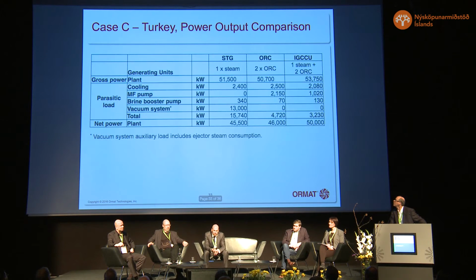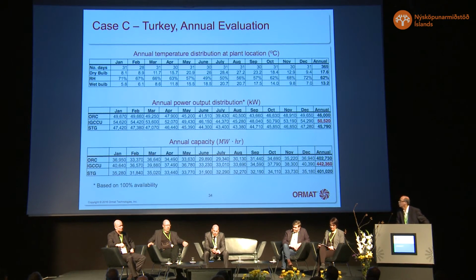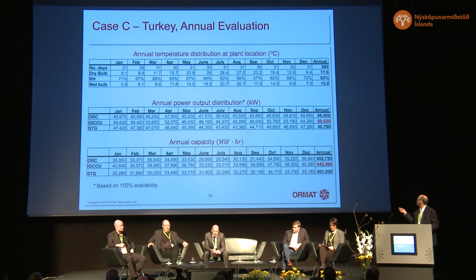I will just go shortly through another case, of high NCG. You can see here that for the STG, the power required to take out the NCG is very high, while in the ORC or in the IGCCU it is very small. So the IGCCU can give 5 megawatt more than an STG. On the total megawatt hours of production, it is above 40,000 megawatt hours more power output.